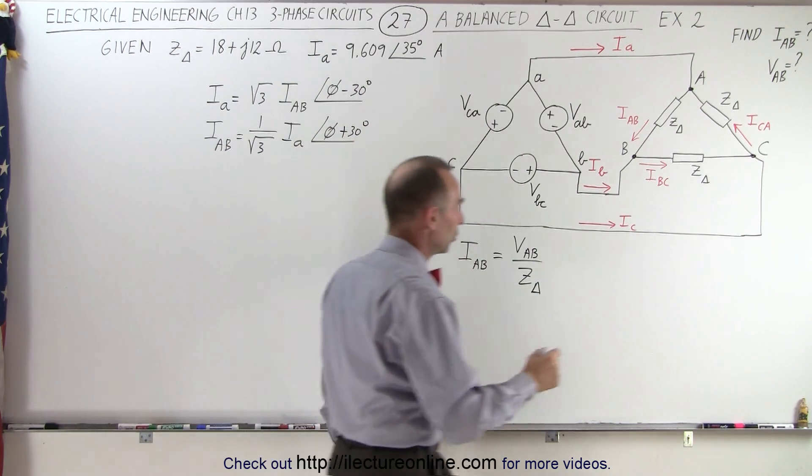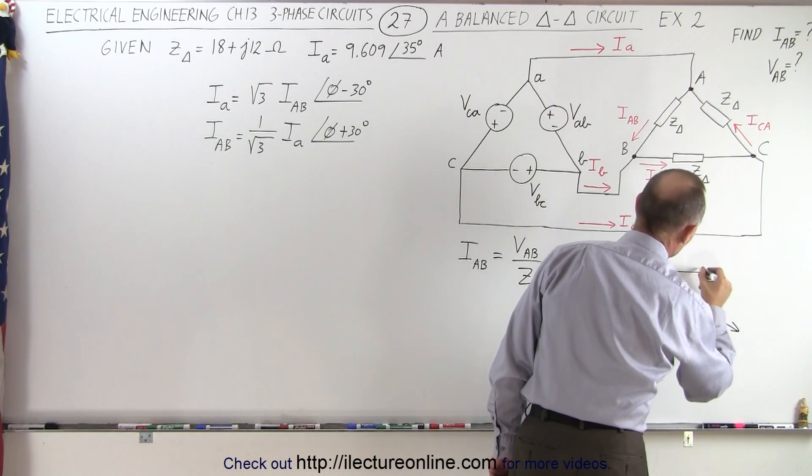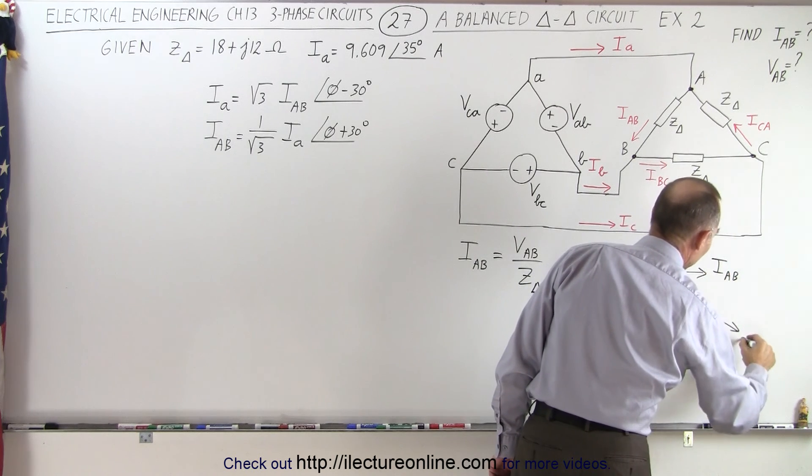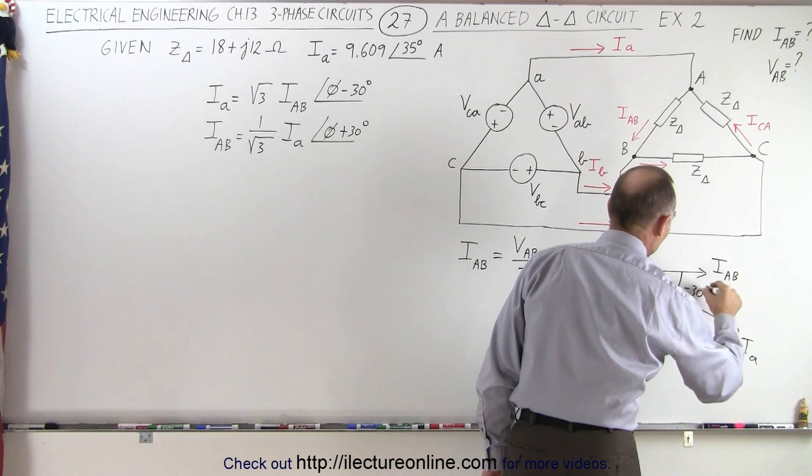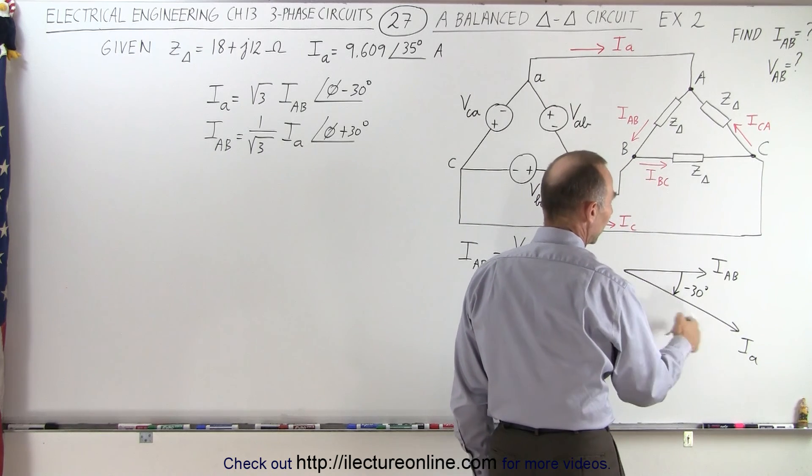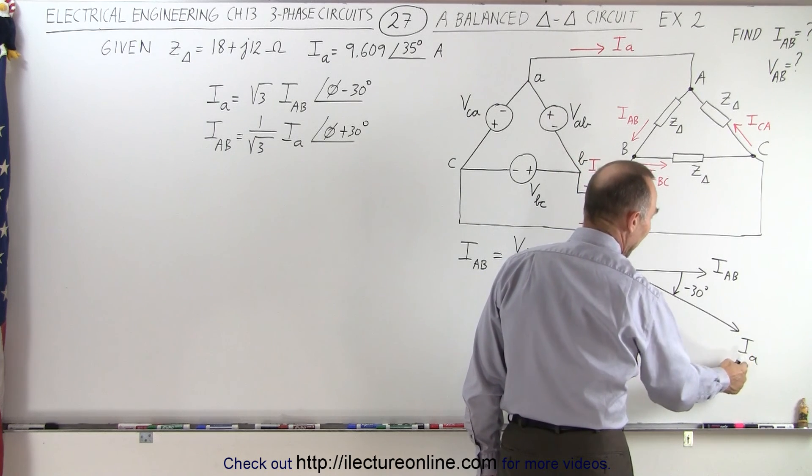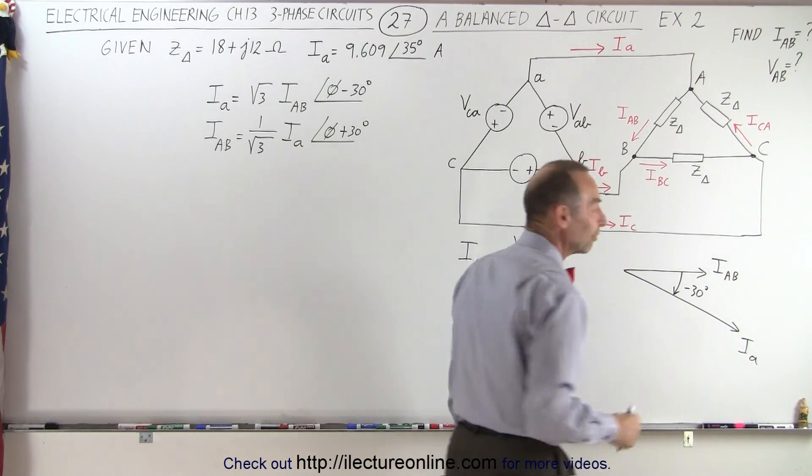Remember, the relationship between the two, if we were to draw that graphically like this, you can see that here we have IAB, there we have IA, and notice the phase difference of minus 30 degrees. So, if we go the other way around, from the magnitude, we divide by the square root of three to get from IA to IAB, and we add 30 degrees to go from IA to IAB in the phase.